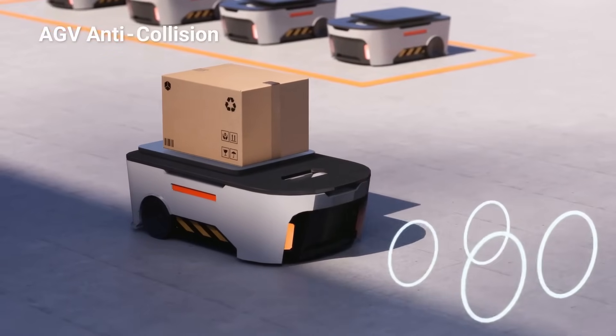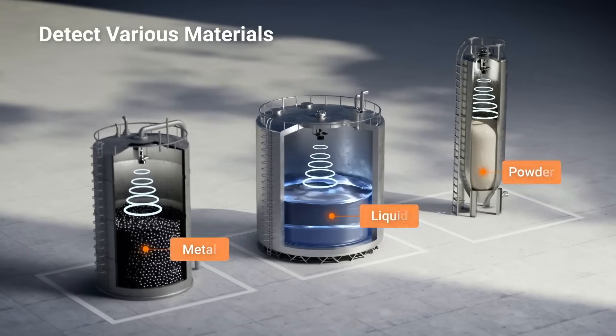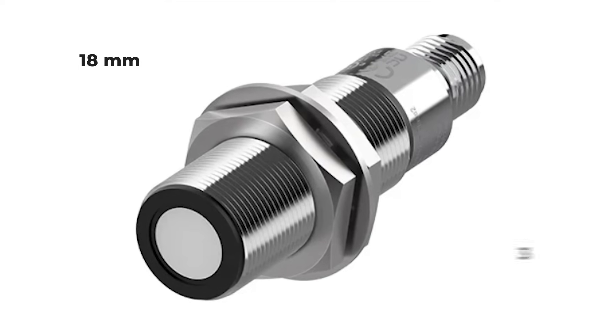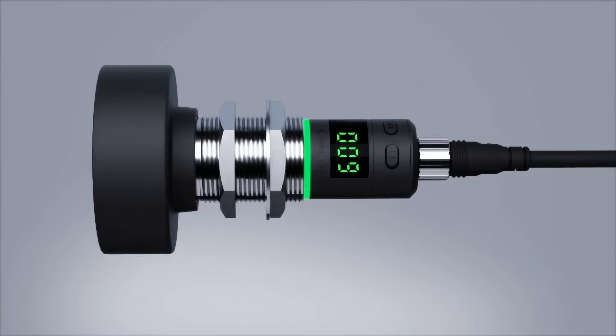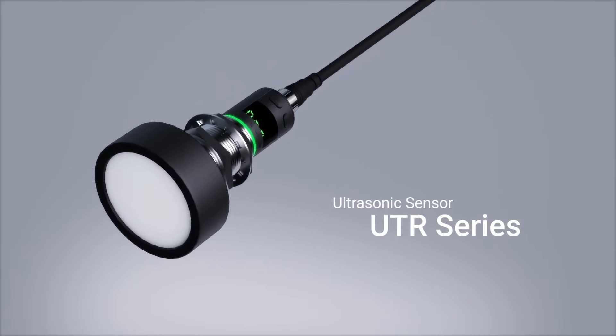Thank you David. The Autonics UTR series sensors offer some pretty cool features. One of which is they are able to detect objects up to 8 meters away and measure various materials like liquids, solids, or powders. Available in 18mm or 30mm stainless steel bodies, they provide digital and analog or purely digital outputs, with analog options supporting current and voltage or current alone.